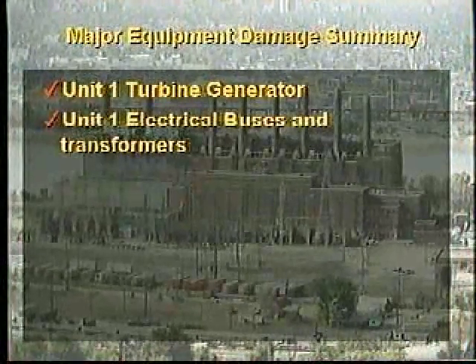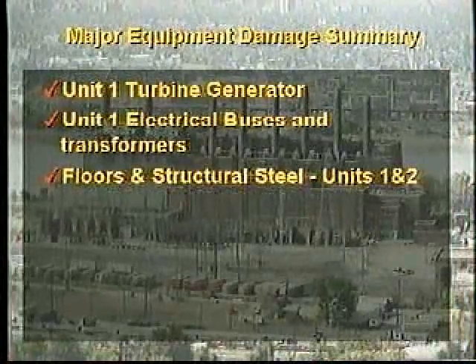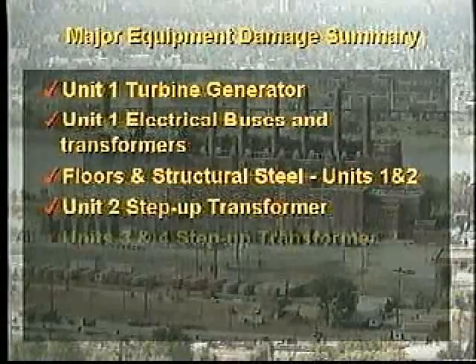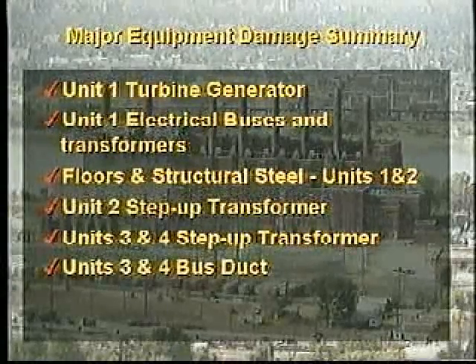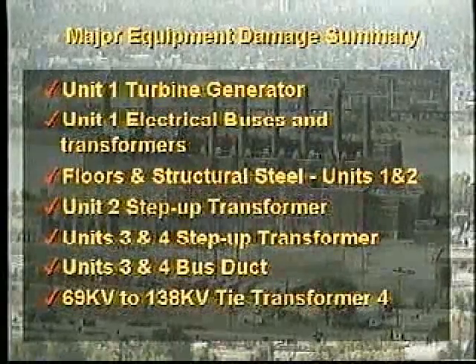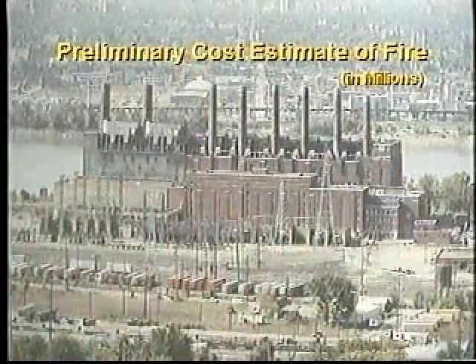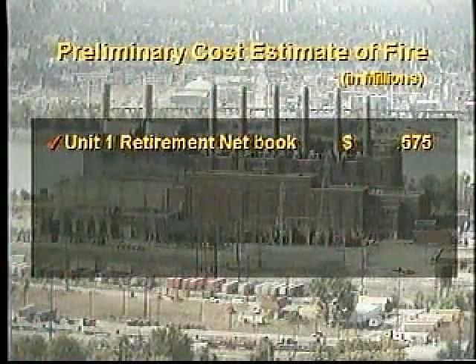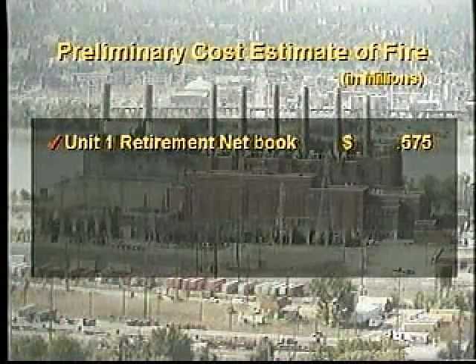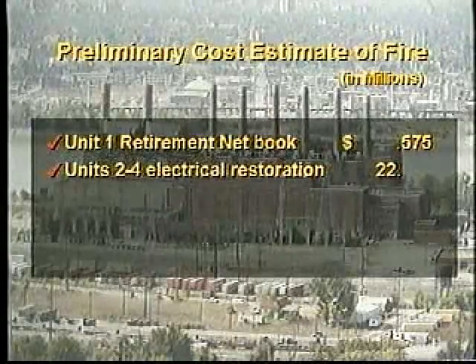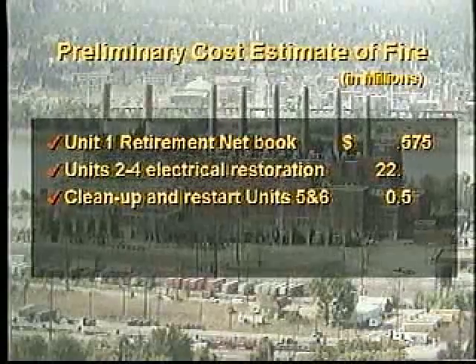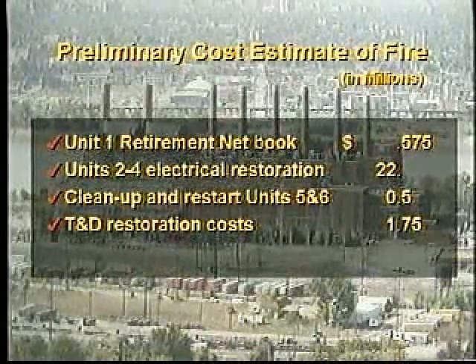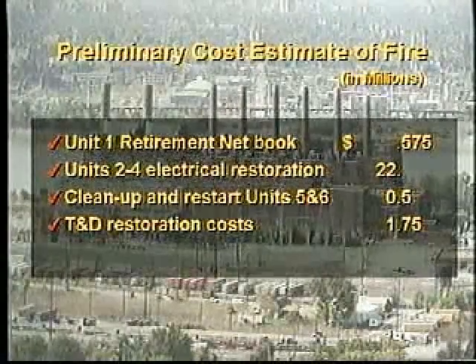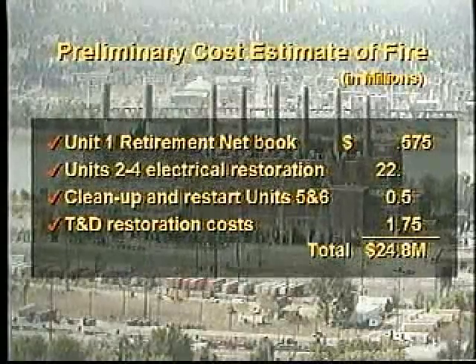A summary of major equipment damage includes Unit 1 turbine generator, Unit 1 electrical buses and transformers, floors and structural steel for Units 1 and 2, Unit 2 step-up transformer, Units 3 and 4 step-up transformers, Units 3 and 4 bus duct, and our 69 to 138 kV tie transformer, number 4. Looking now at our preliminary cost estimate of the fire, below I'd like to summarize what those are. Unit 1's retirement cost is around $600,000. Units 2 through 4 electrical restoration is estimated at $22 million. Cleanup and restart of Units 5 and 6, $500,000. And T&D restoration cost as a result of this event, $1.75 million. For a total cost of this event, approximately $25 million.